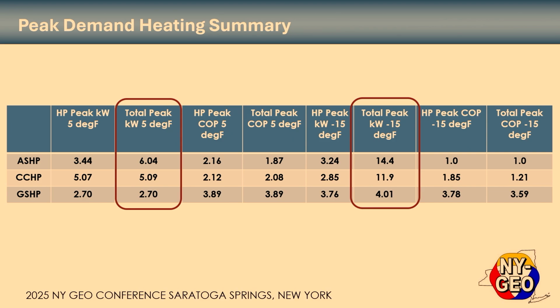The ground source heat pump is at 2.7 again because, on the chart, for the efficiency, we're able to work at 32 degree entering water temperature instead of minus 15, and there's a pretty good advantage for that temperature. So here we are with auxiliary heat put in at 5 degrees. And you can see that the air source cold climate heat pump, I should say, just barely has a little bit. If you remember that chart, it essentially was running full capacity at 5 degrees, had very little electric heat. And so that's what you're seeing here, essentially full capacity. It was sized for a 5 degree balance point.